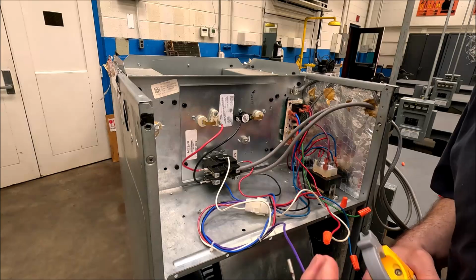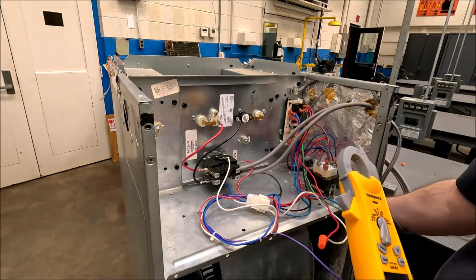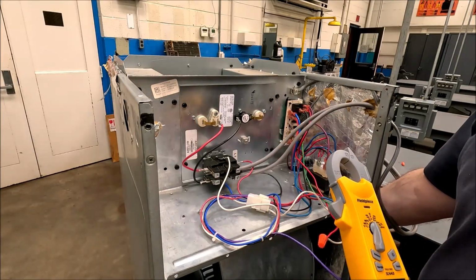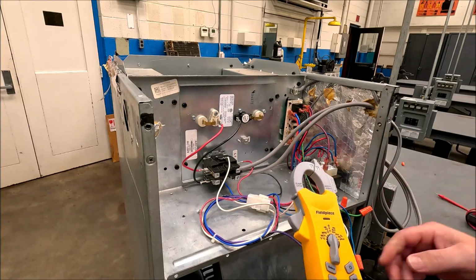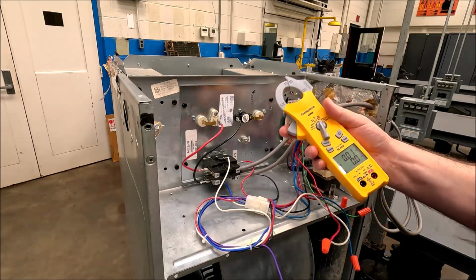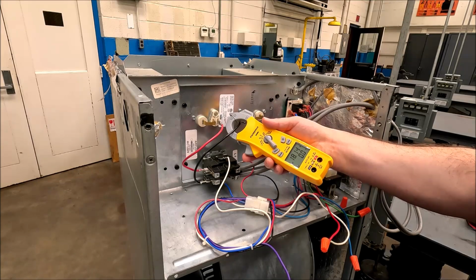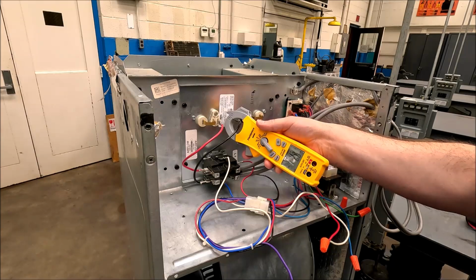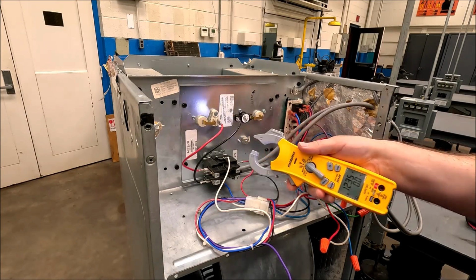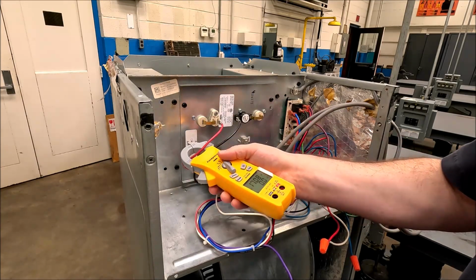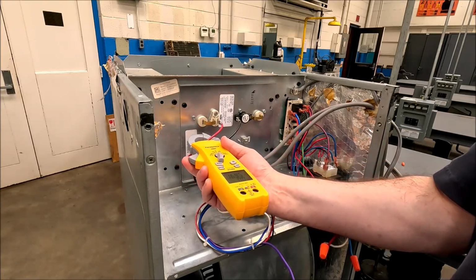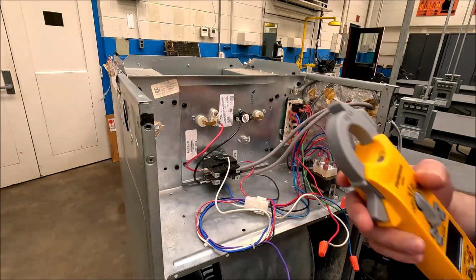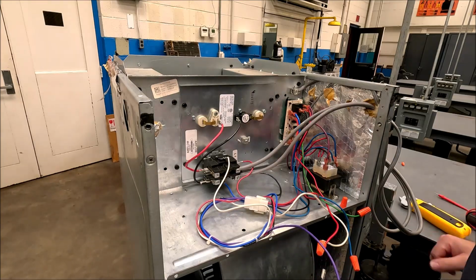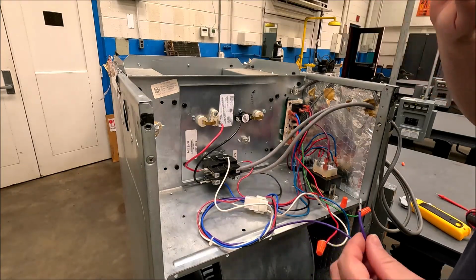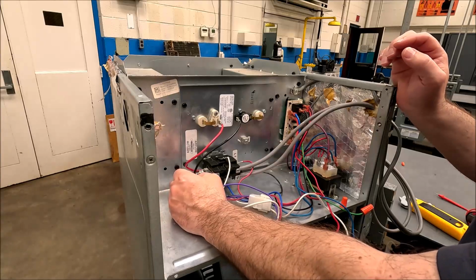So I'm holding this high voltage one out. I'm gonna turn on the breaker and the heat strips are gonna turn on. There they go. So if I check the amps on this black wire, 18, 17.9, there we go. And if I check it on the red wire, it's 17.9. So basically the same thing, but I can feel the heat coming off of this. So I'm gonna go ahead and plug this blower back on.